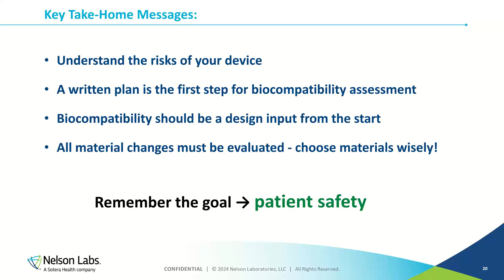Biocompatibility should be a design input from the start, so we need to make sure that we think about it as a critical step when we choose our materials. And all material changes must be evaluated, so choose your materials wisely. And remember, the main goal here is patient safety. That is what we strive for. We want to make sure that when you have your final finished device, it is not going to inadvertently cause harm to the patient.